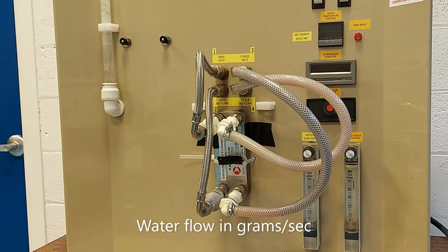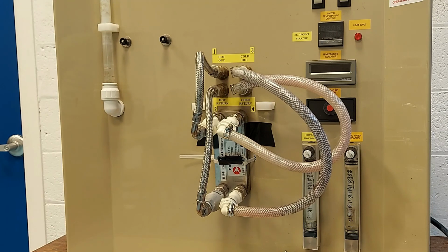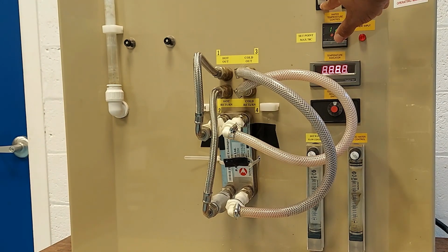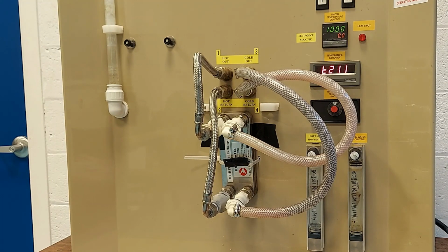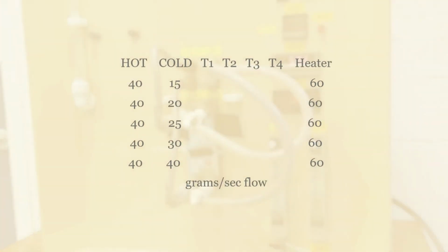So now that we're configured for our countercurrent flow, we would turn the flow back on. Then we'd turn the machine back on. We would then wait for equilibrium to take place. Now we would go ahead and take our readings with our hot water constant at 40 grams per second, and our cold water will be varied from 15 to 20, 25, 30, and then 40 grams per second. So let's begin.